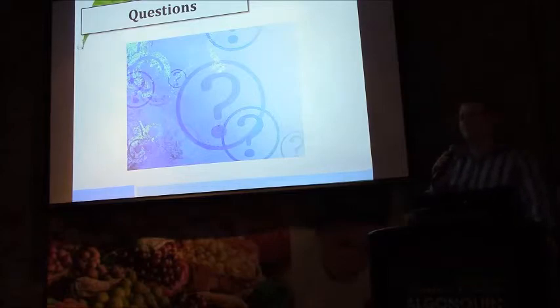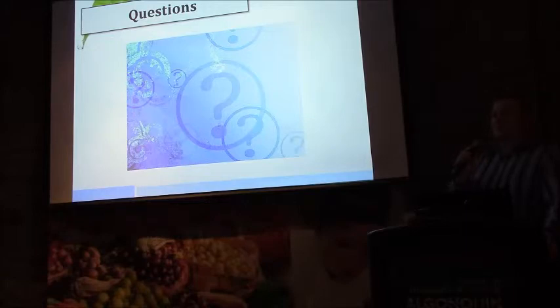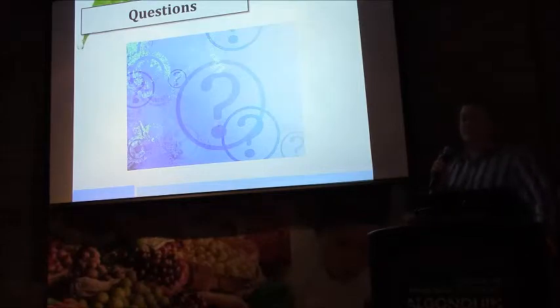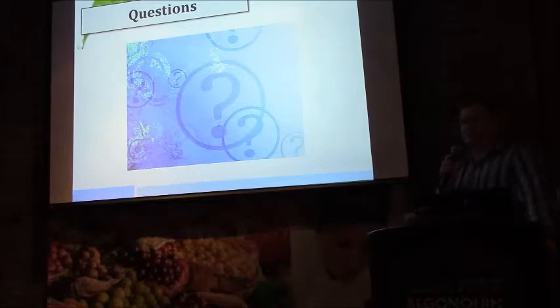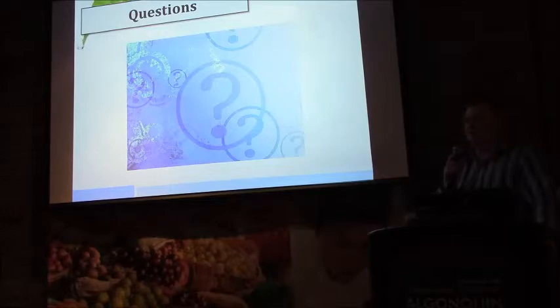You half answered my question, which is where the thermostat is kind of going to go, but what are you driving with that thermostat? What would you prefer to drive? The valve going into the water valve. The water valve principally. So the primary air is needed for a min vent for ventilation, of course, for the space, unless it's a space where we're isolating the primary airflow because of occupancy and the risk of overcooling, like a meeting room where the primary air is a higher percentage. But fundamentally, it would be water. Air side would be second. It could be a two-stage stat as well, so primary air is stage one. If we don't have a condition of loss of dew point in the space, then the chilled water can come out as stage two.